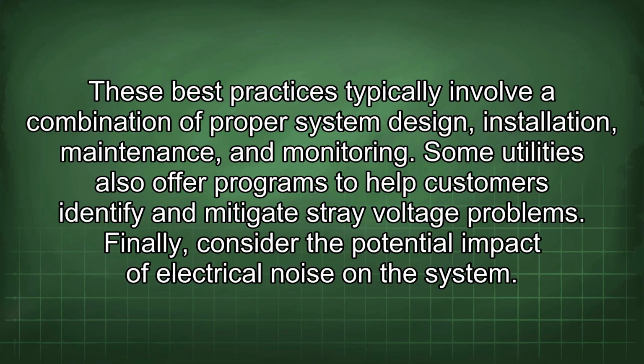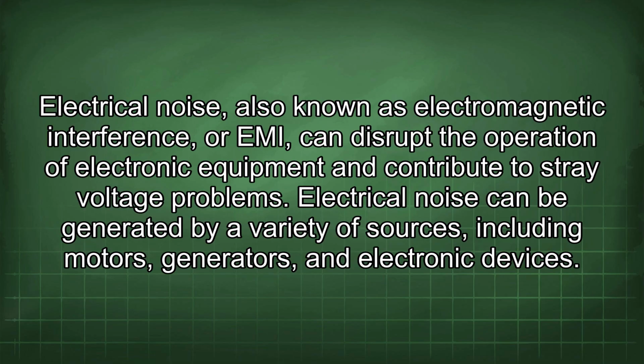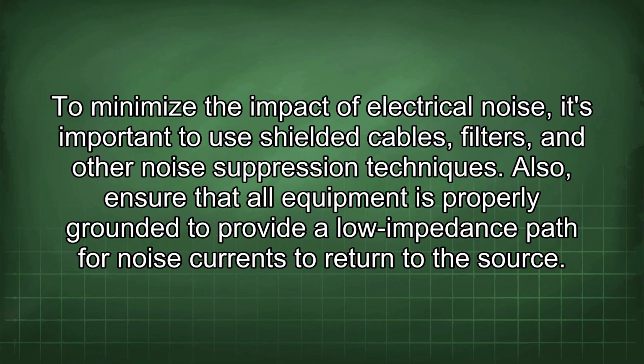Finally, consider the potential impact of electrical noise on the system. Electrical noise, also known as electromagnetic interference, or EMI, can disrupt the operation of electronic equipment and contribute to stray voltage problems. Electrical noise can be generated by a variety of sources, including motors, generators, and electronic devices. To minimize the impact of electrical noise, it's important to use shielded cables, filters, and other noise suppression techniques.